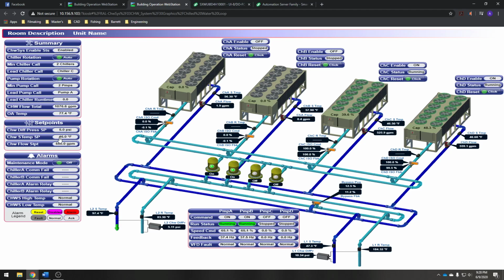That's something we did not talk about, the set point. The chiller's primary job, the only thing it cares about, is this supply temperature right here, 46 degrees. The compressors in here will stage up and down accordingly, which is this capacity here. As more compressors kick on, the capacity increases, and it wants to maintain 46.4.